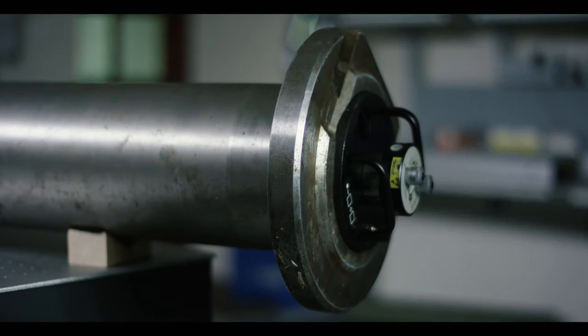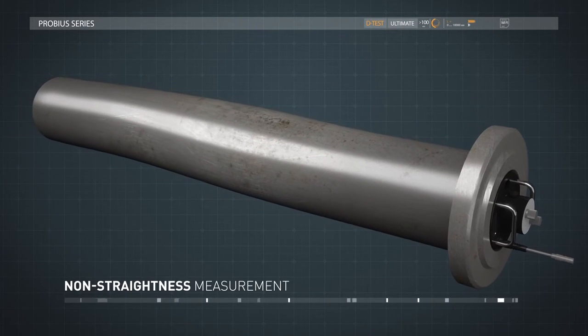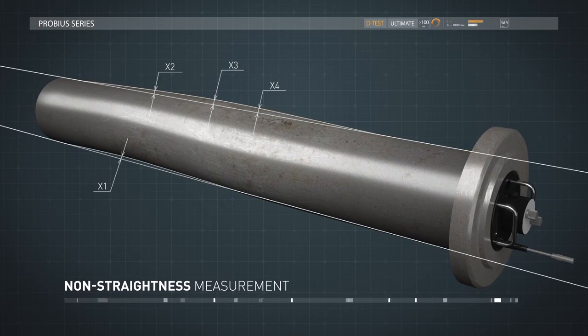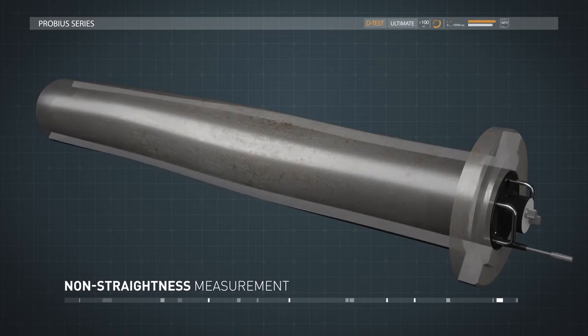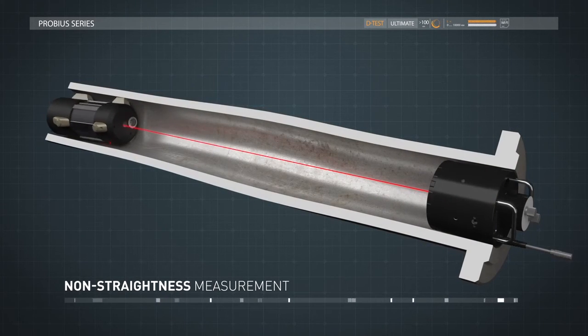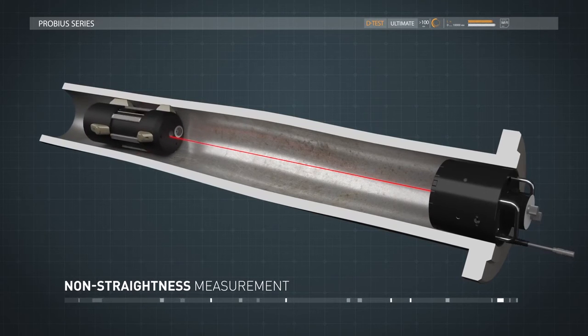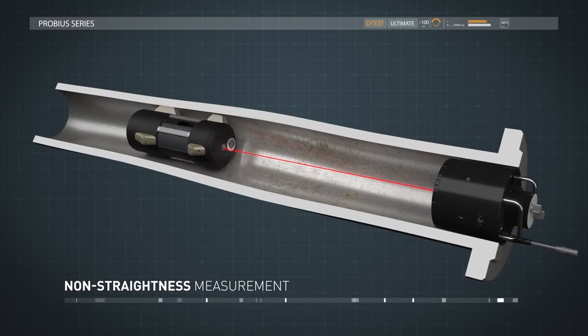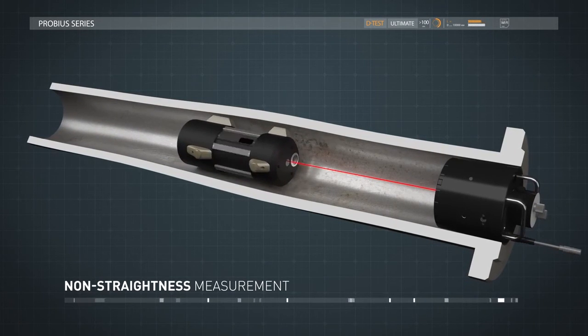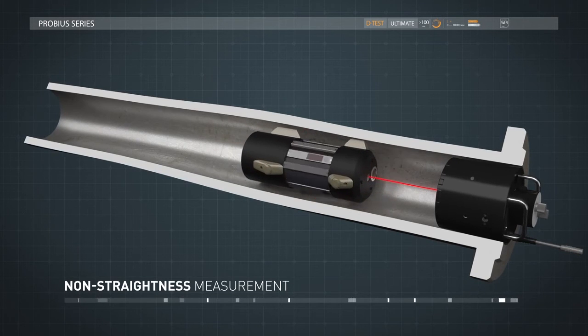To measure non-straightness, you insert the laser emitter from one side of the measured object and ProBius from the other side. The laser emitter creates a very stable base axis inside the object and copies the shape of the profile when it moves inside the object. The photosensor detects the position of the laser beam while software calculates the real-time deviation from the base axis.